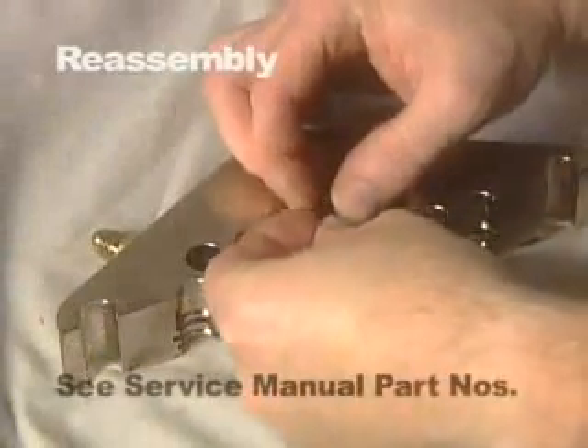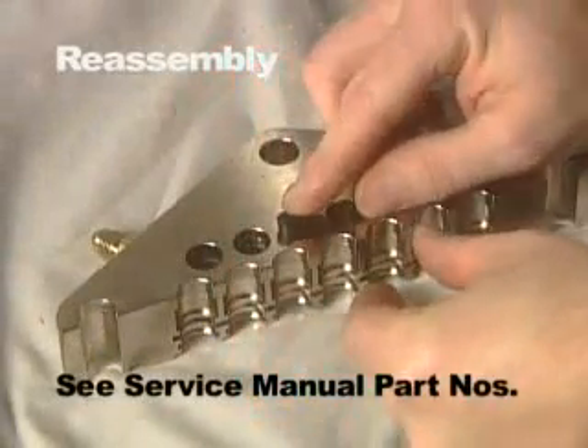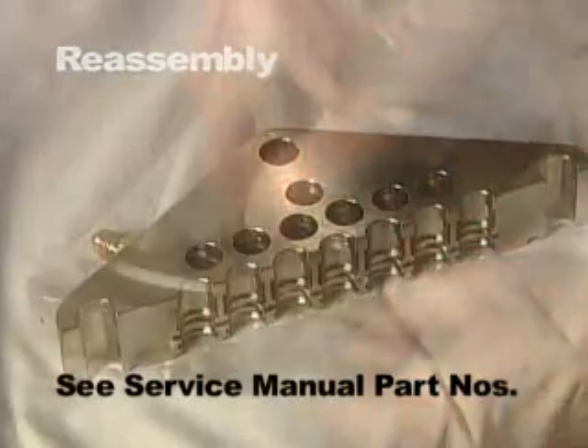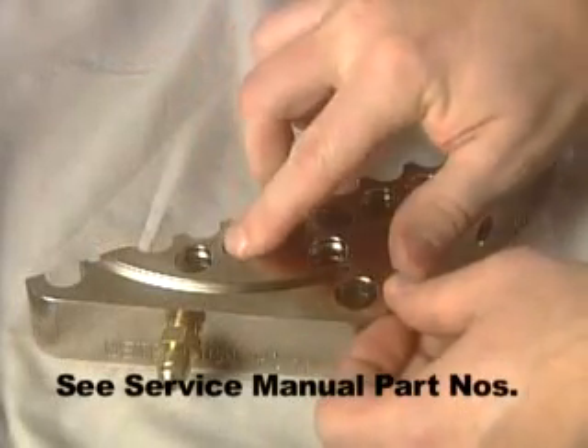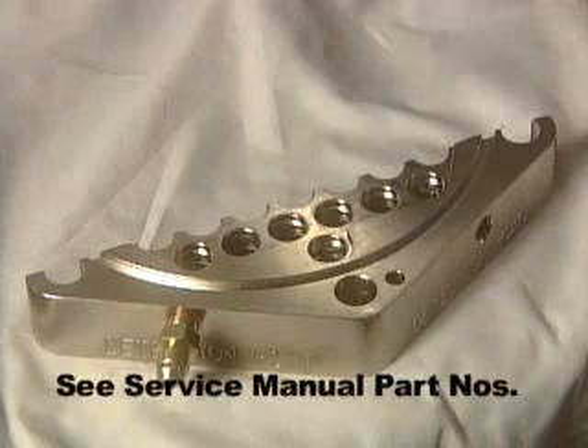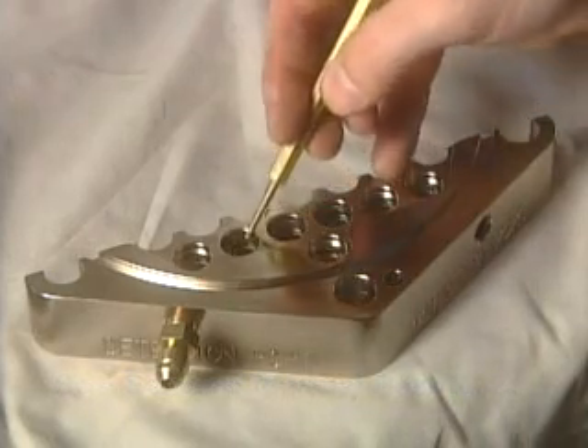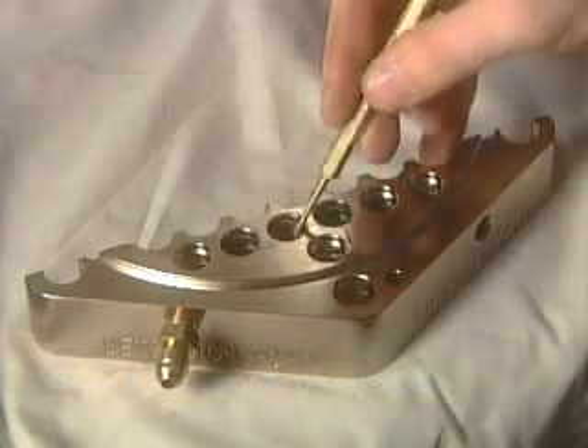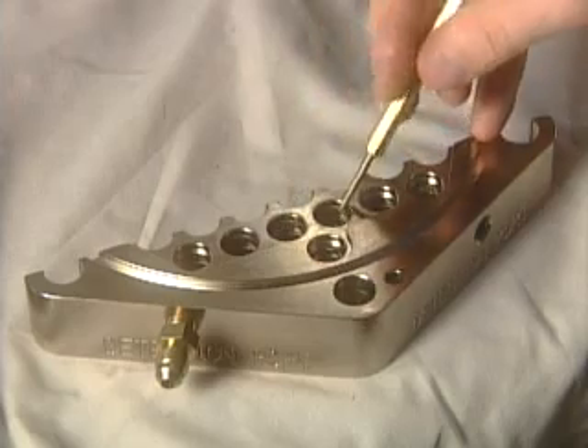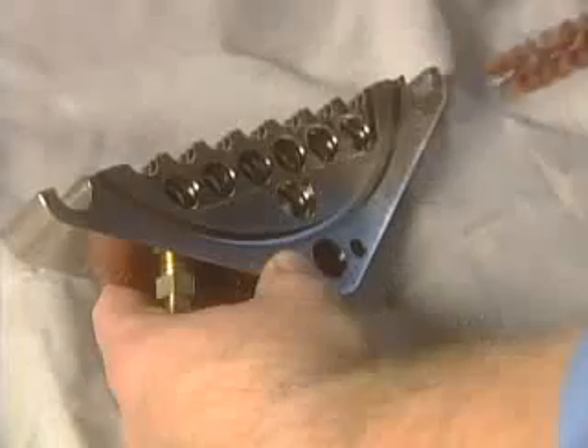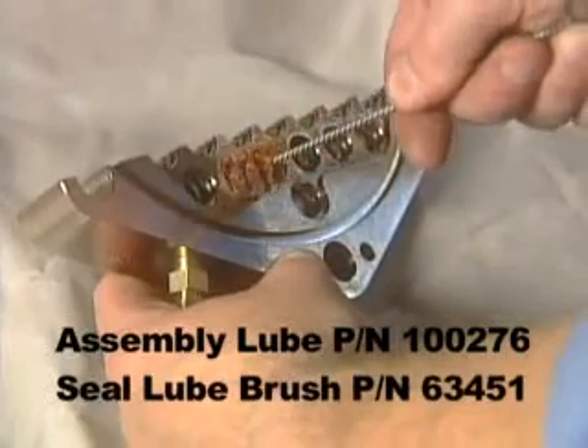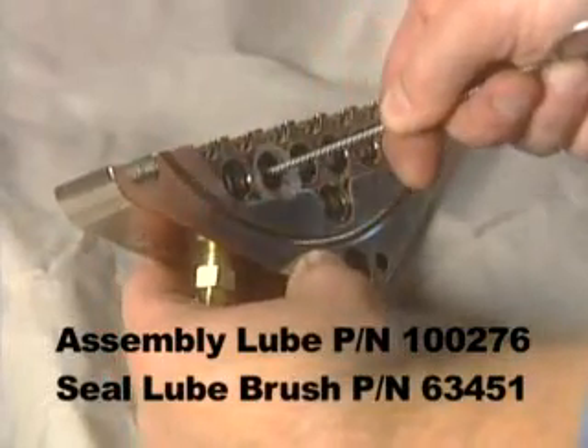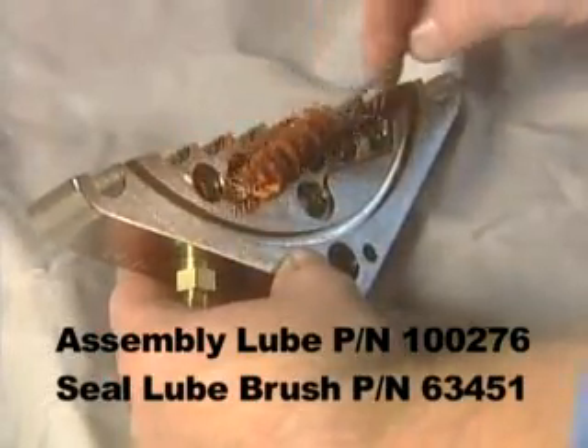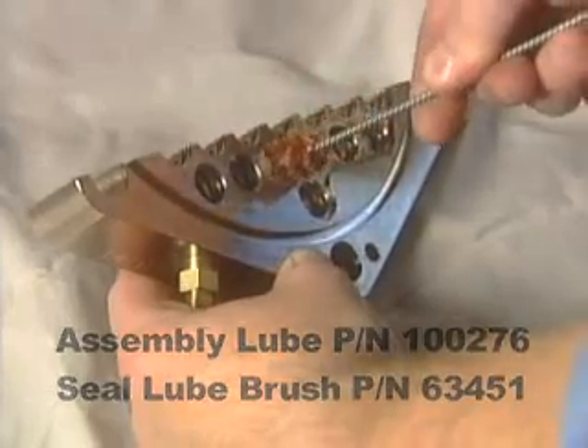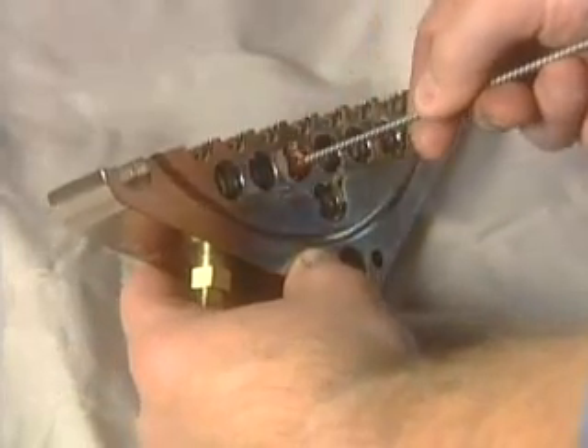Carefully install new seals into the clean headers. The wider seals go into the wider seal grooves, and the more narrow seals go into the inner seal grooves. Inspect the seals for proper seating in the grooves, and also for any debris that might prevent a good seal. Now lube the seals with the lubricant and brush specified in the System Protector service manual. Adequately lube the seals, but do not use excessive amounts.